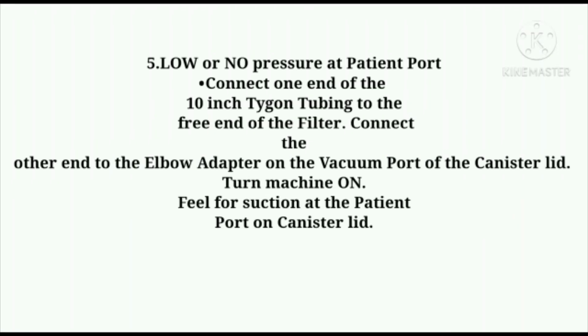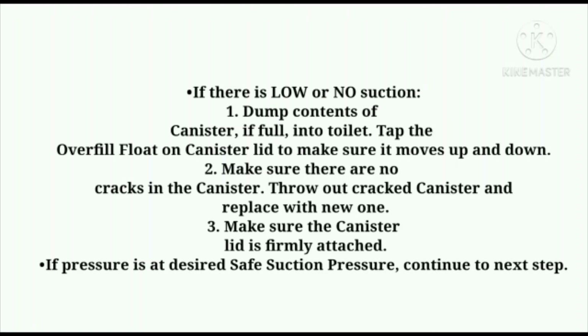The fifth problem, low or no pressure at patient port. So, you must connect one end of the 10-inch Tygon tubing to the free end of the filter, connect the other end to the elbow adapter on the vacuum port of the canister lid, turn machine on, feel the suction at the patient port on canister lid. If there is low or no suction, you must dump content of canister.